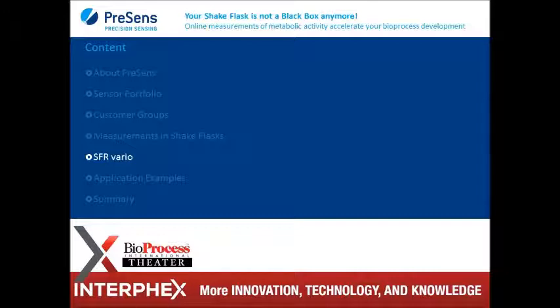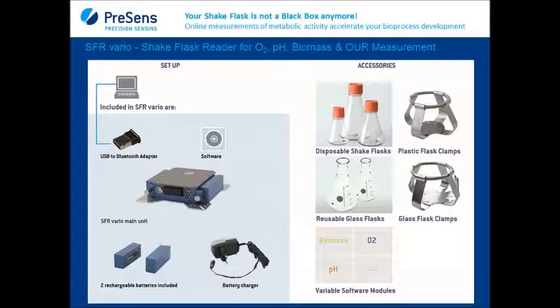The SFR Vario that I was talking about comes with certain accessories. Like I mentioned, it comes with the software. The software is brand new. It's very easy to handle. It has very convenient data evaluation functionalities. The complete system is absolutely wireless, so data communication is via Bluetooth to your PC. It's battery powered. It comes with 2 batteries, but it will run with 1 battery as well. So if you want to do a measurement that is very long and exceeds the battery lifetime, you can take out 1 battery, recharge it, put it back in, recharge the other battery, and you never have to stop your measurement.